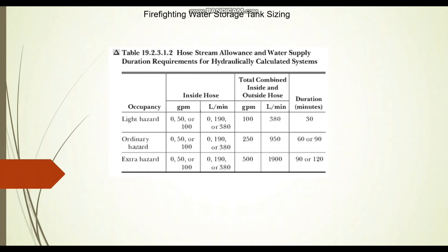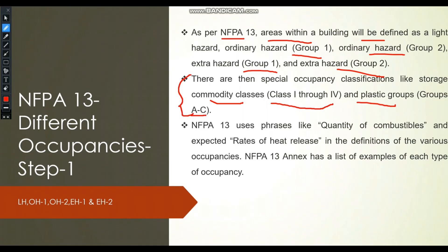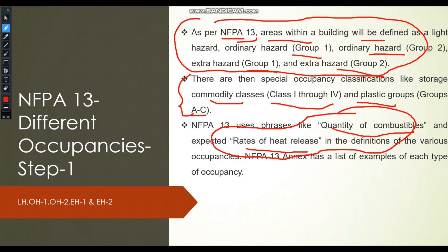Now we will see a simple example of how to identify the hazard from different applications, then proceed to tank sizing. As per NFPA 13, areas within a building are defined as light hazard, ordinary hazard group 1, ordinary hazard group 2, extra hazard group 1, and extra hazard group 2 — five categories. There is also a special commodity class (class 1 to 4) and plastic groups (A to C) for special projects like warehouses. Overall, NFPA 13 classifies hazard based on quantity of combustibles and rate of heat release.